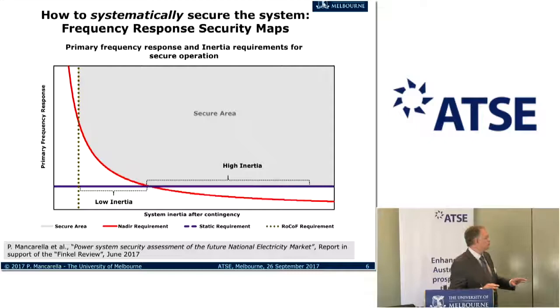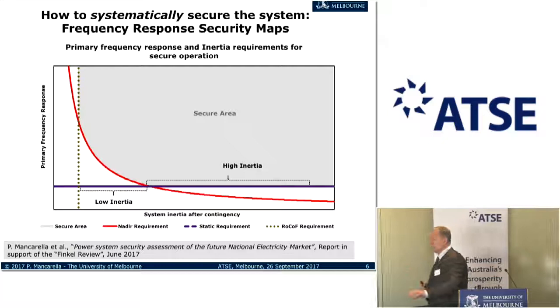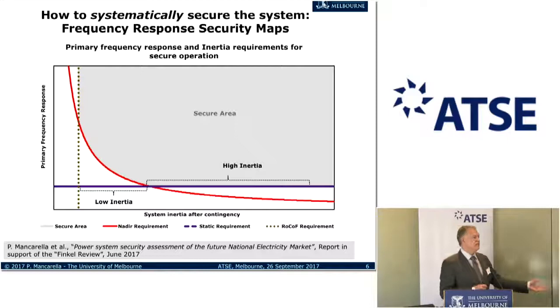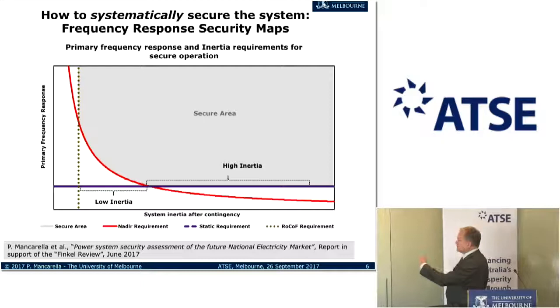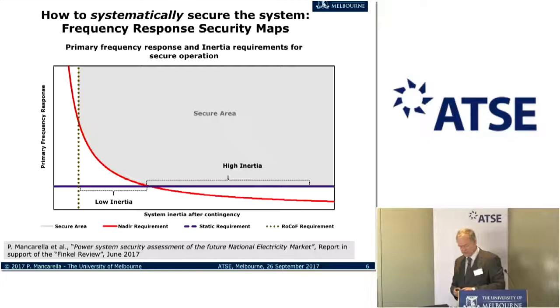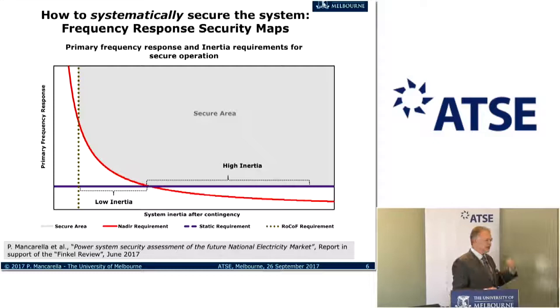The moment we move more towards a low inertia system, these other constraints start to play a role. The first constraint we'll see is how far the frequency can actually drop while still maintaining stability in the grid—that's the nadir point of this red curve, and it's hyperbolically related to the size of the inertia. Then at a later stage we'll see how the rate-of-change-of-frequency comes into play. If we really have low inertia, that will actually overtake the nadir frequency requirement.